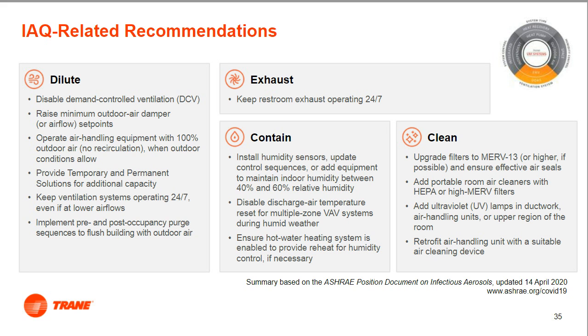Lastly, ensuring that the air in a system is properly cleaned is perhaps the most important pillar of indoor air quality. By ensuring that a system has adequate MERV-rated filters for occupied spaces, as well as other methods of airborne contaminant reduction, such as UV lighting, the occupants of a space can rest assured knowing that the building's HVAC system is not only providing comfort cooling, but is also addressing indoor air quality concerns. As always, please be sure to size and design any method of filtration in conjunction with the equipment static pressure restrictions. This is important also when sizing for VRF terminal zone units.